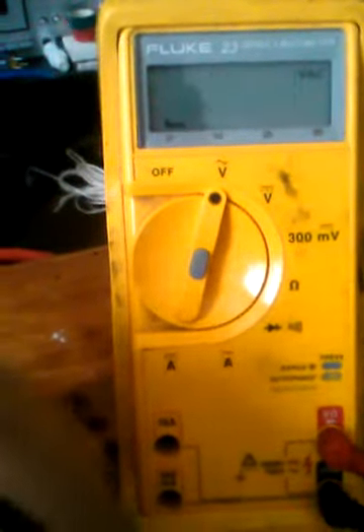I don't know why this is reading 32 volts, but that's not good. It should go to 0. Let's try the neutral side. Maybe because this outlet tester is in the way. That's reading 59 volts, which is not good as well.